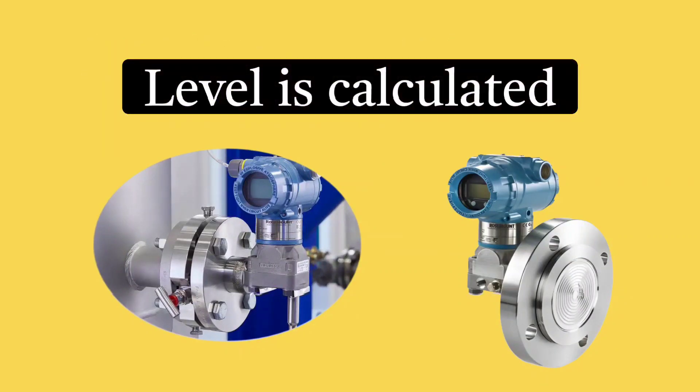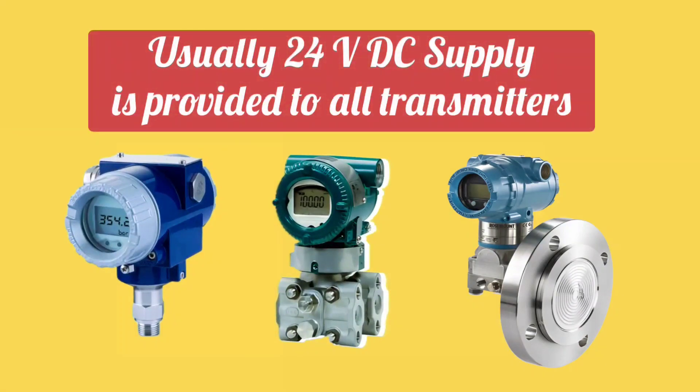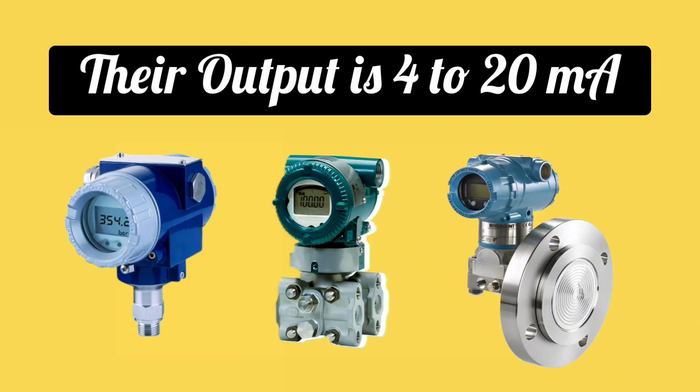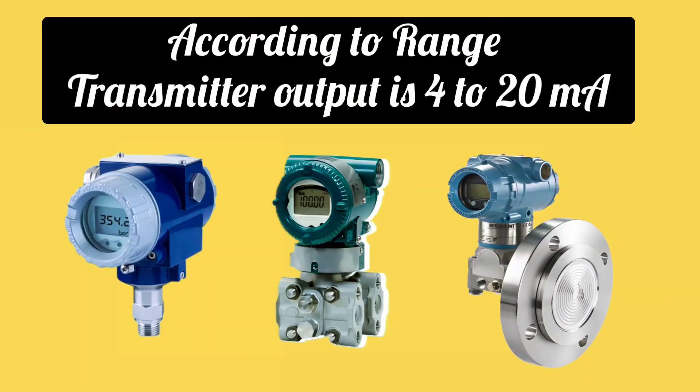Friends, usually 24 volts DC supply is provided to all pressure transmitters. And their output is 4 to 20 milliampere signal. According to the range, these transmitters give 4 to 20 milliampere output.